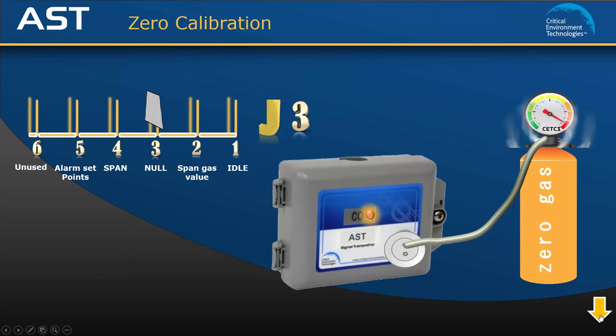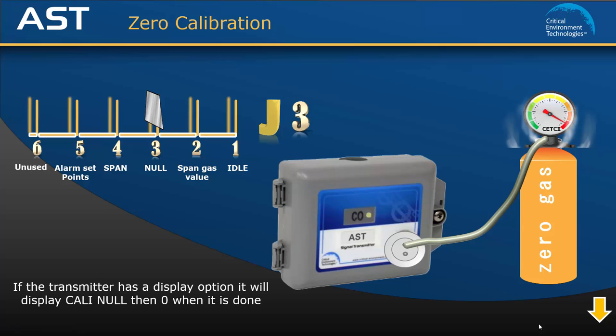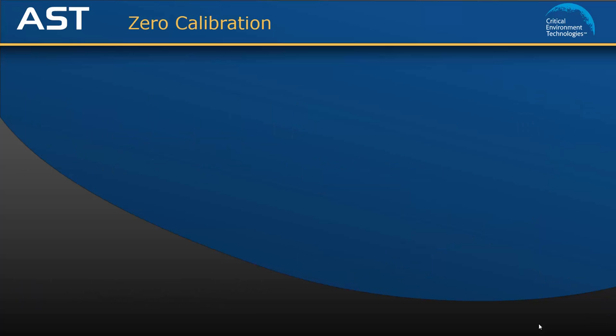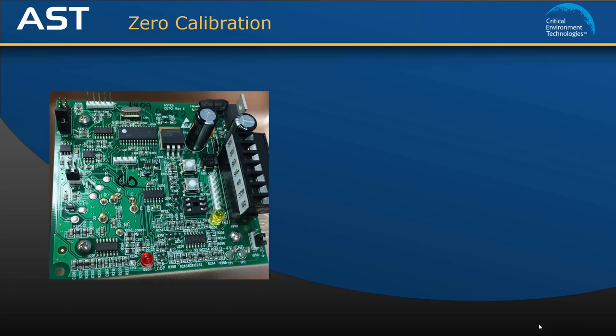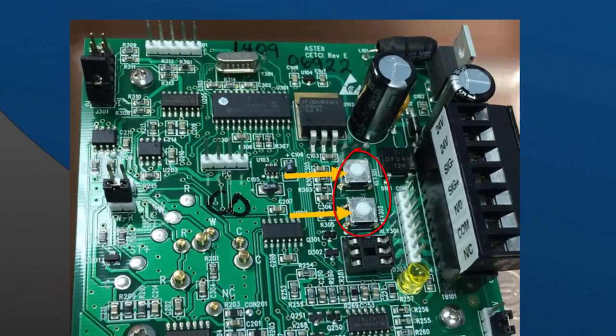Once the countdown is finished and the AST has adjusted the null value, the LED will change back to solid green. If your AST has the optional display, it will show Cali null. Move the jumper back to the idle position and then remove the zero air cylinder. If after flowing zero air the circuit does not settle within the 20% tolerance value, you can continue the null procedure by performing an unlock function. To do this, push both the up and down buttons together. The zero calibration procedure will then continue.